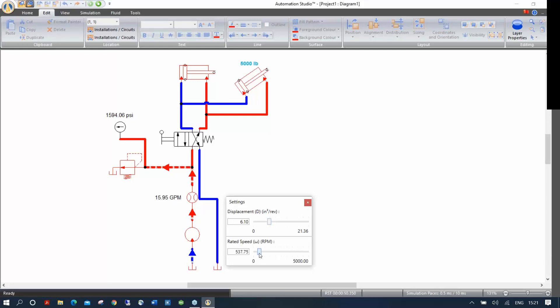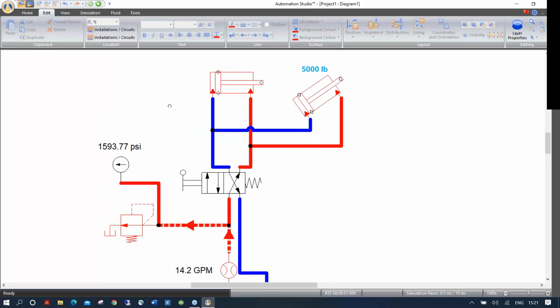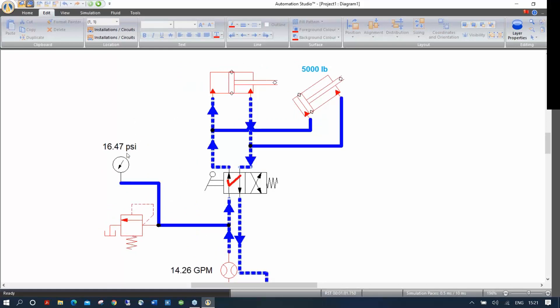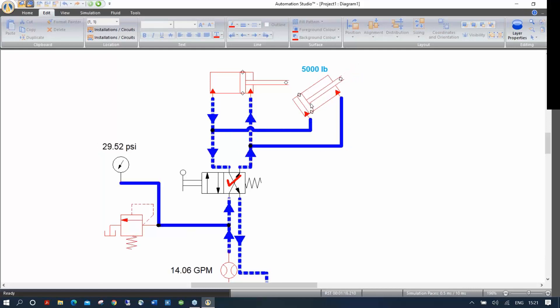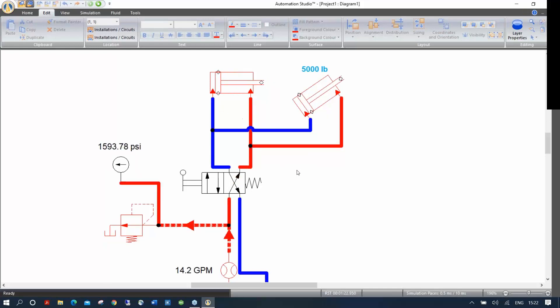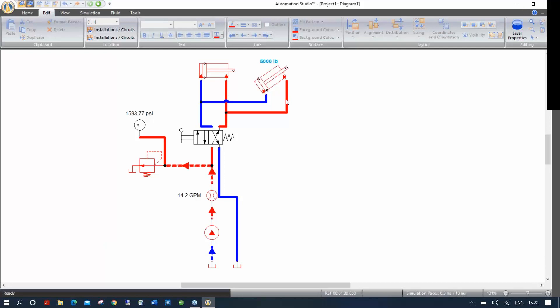It's good to show students the effect of pump size and speed on pressure versus flow. With about 14 GPM now, I'll simulate the circuit. The first cylinder extends at about 15-16 PSI; the second requires about 280 PSI to push the weight up. When they retract, the loaded one gets pushed by the weight first. This demonstrates how circuit changes — like adding a throttle valve — affect back pressure and speed.